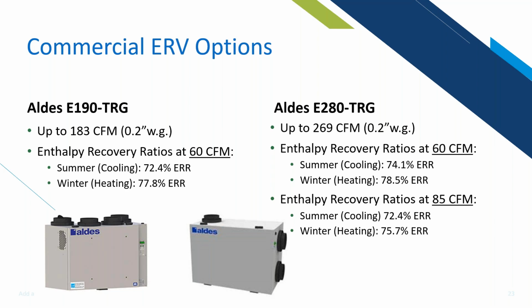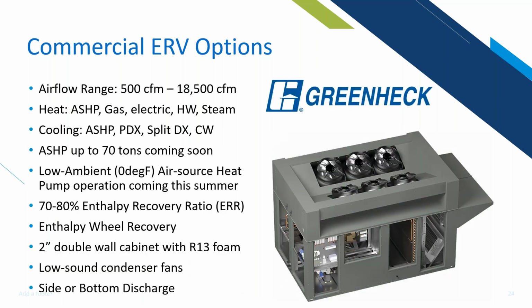So another really amazing product that we have coming out, and this has actually been popular in our market for a while now, but we have some updates that I'm excited to share. To be fair, these are a little ways out, but in May of this year, we'll be able to provide the Greenheck ERV option with an updated air source heat pump. And that heat pump will work with 0 degree outside air. That's an air source heat pump up to 70 tons, and we'll actually be using this with the new refrigerant. Next January we will require an A2L refrigerant, and GreenHeck will be providing this with R454B refrigerant.